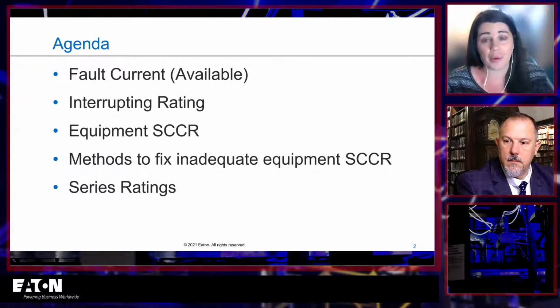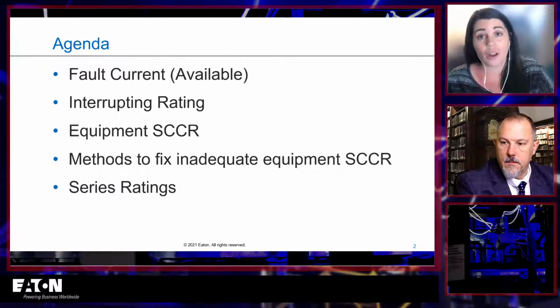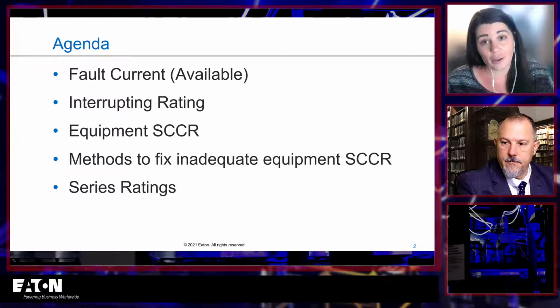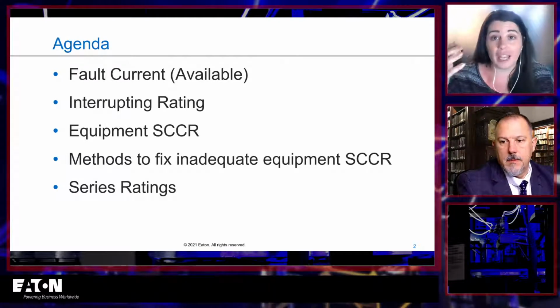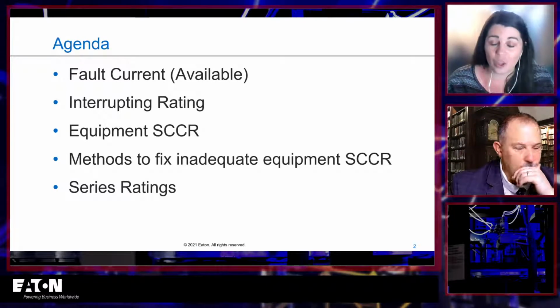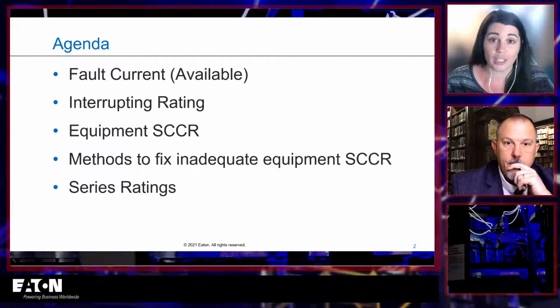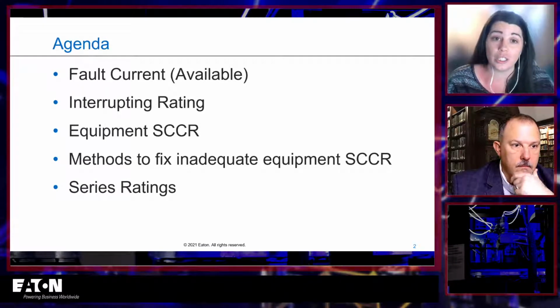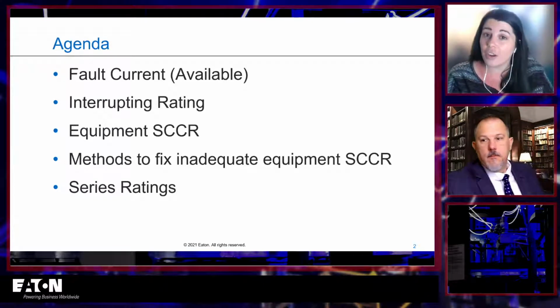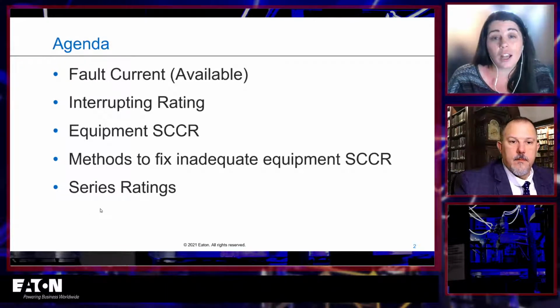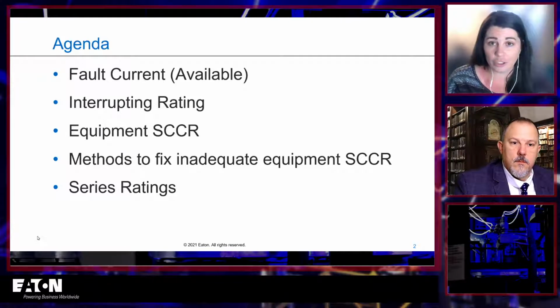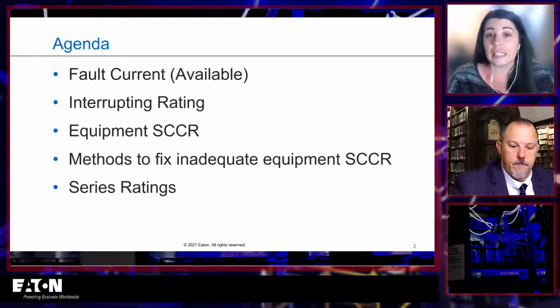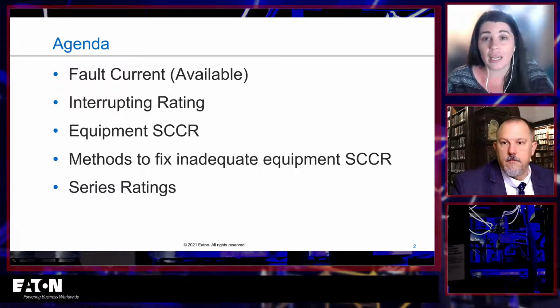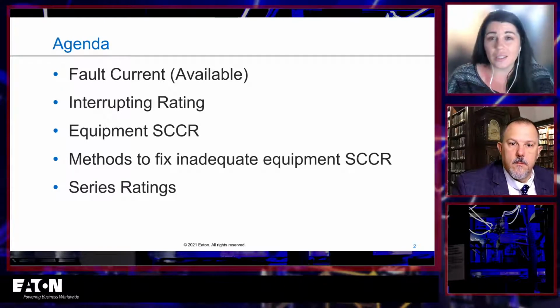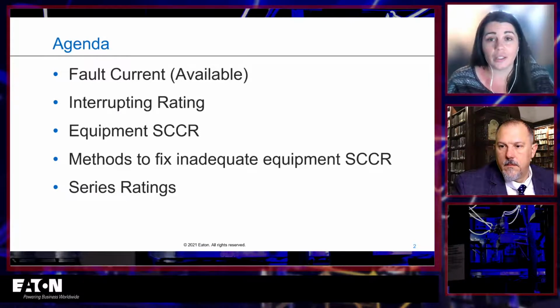What people are usually reaching out to me for is methods to fix inadequate equipment SCCR, right? It's all too common that it comes out that we've installed a piece of equipment and its short circuit current rating is lower than the available fault current. Now what do we do? So we'll talk about some engineering methods we can use for that, and then we will talk a little bit about series ratings too, because that's usually sort of the NEC requirements for series ratings: when we can and cannot use fuses to help us with an inadequate short circuit current rating.